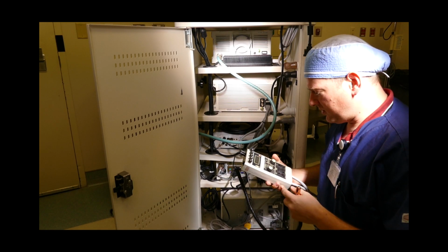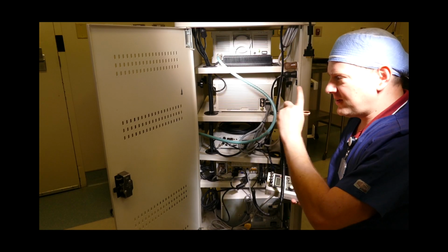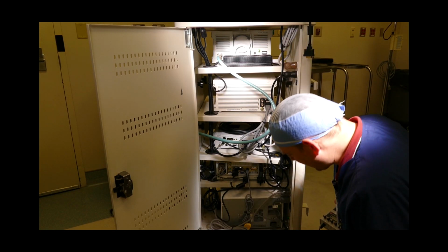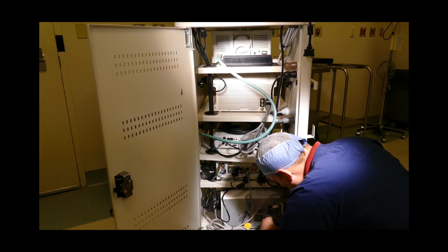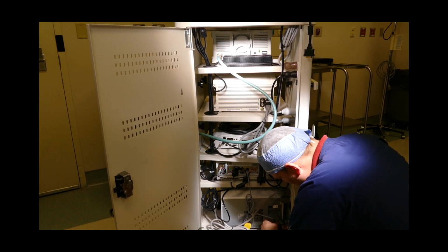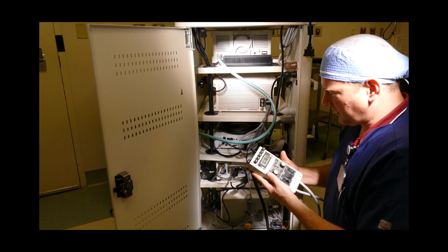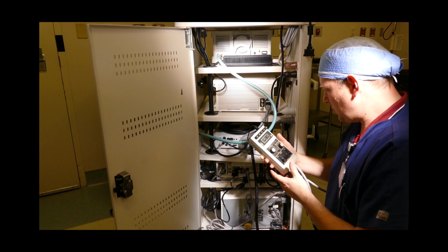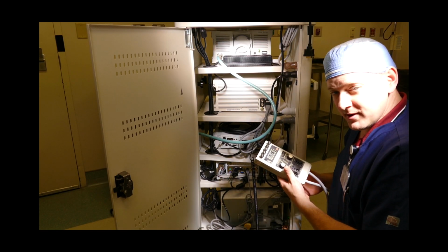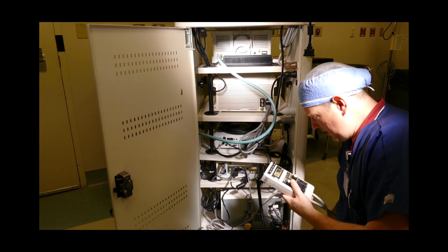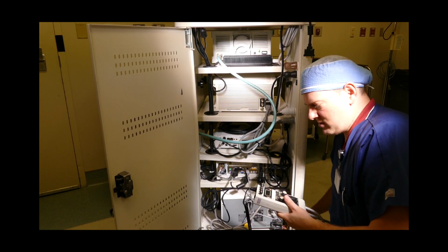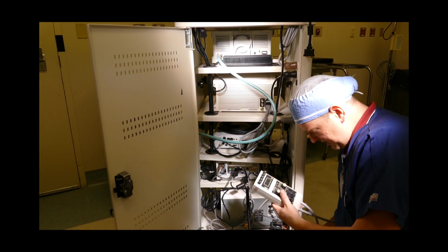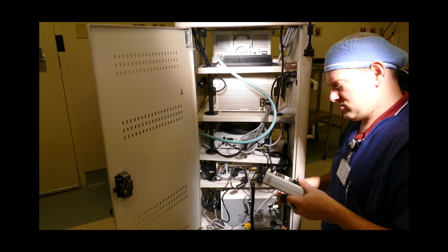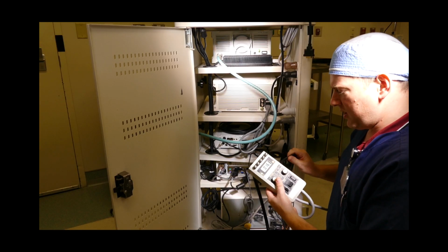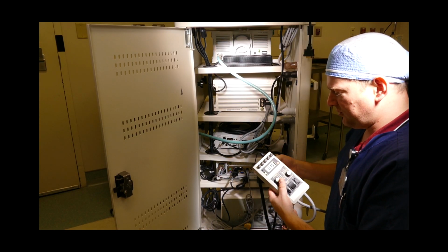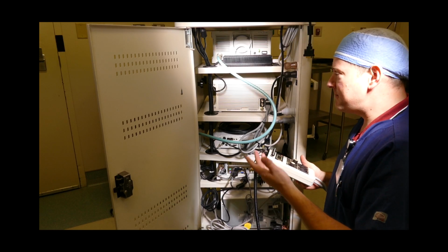So the first test is going to be an earth resistance test, and I'm going to test the cabinet itself. So I'm going to find a good ground. I think I have one down there. Yes, I do. It's 0.16 of an ohm. So we are good. And now the other part of the test is I have to flex the cord at both ends. So I'll start here with the equipment side. 0.15, 0.16, and here at the plug side, I got 0.19, 0.25. So that tests the cabinet.